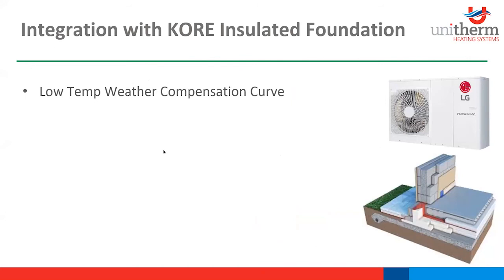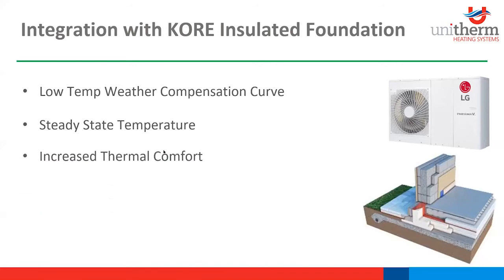So now we can utilize the thermal mass to run our heat pump with a low temperature weather compensation curve. So we can charge the floor so it can radiate throughout the day. We can get a steady state temperature. So optimum performance can be gotten from the machine by charging the whole slab with low flow temperatures of 26 to 32 degrees. So basically leaving your system open, letting it run when it wants.